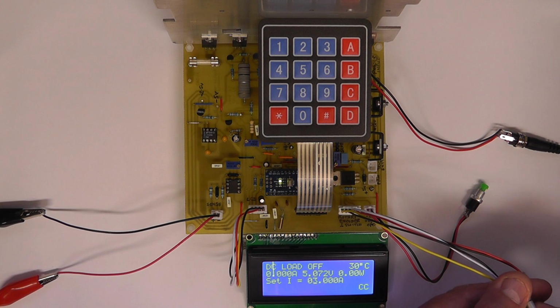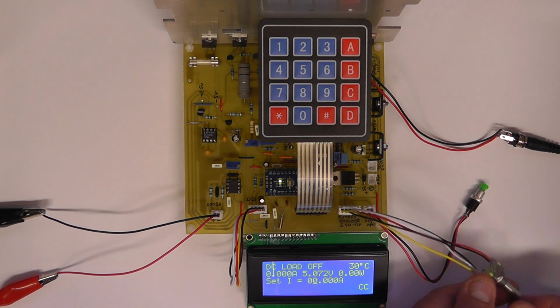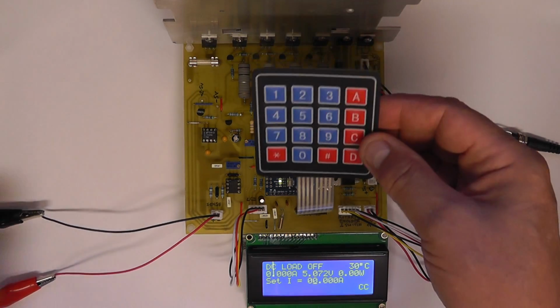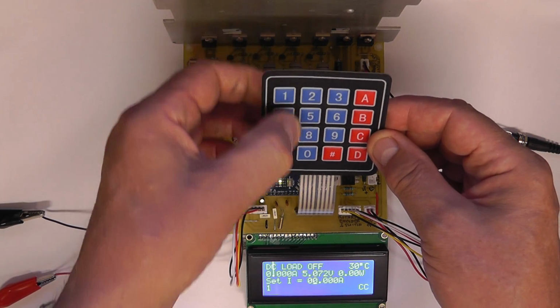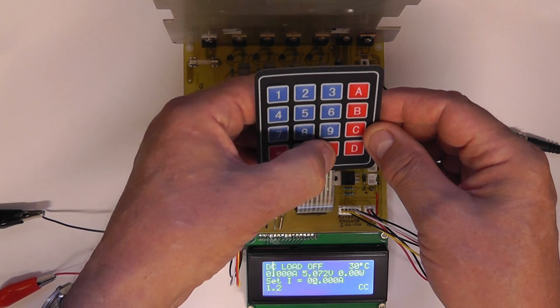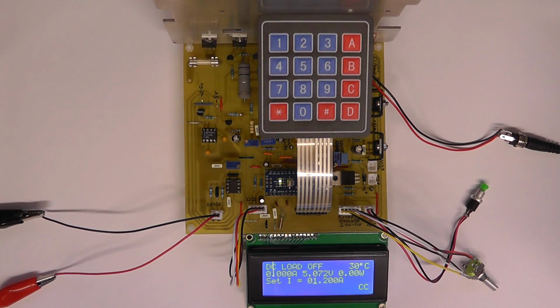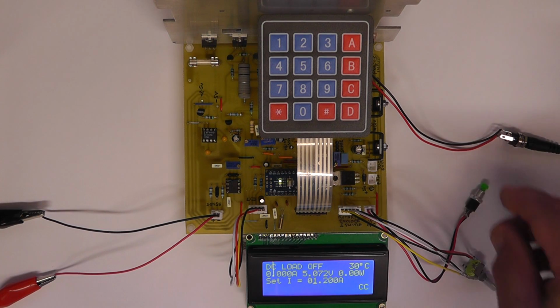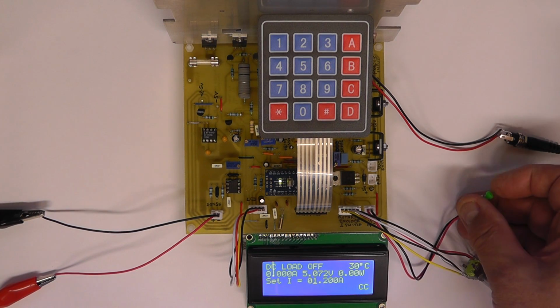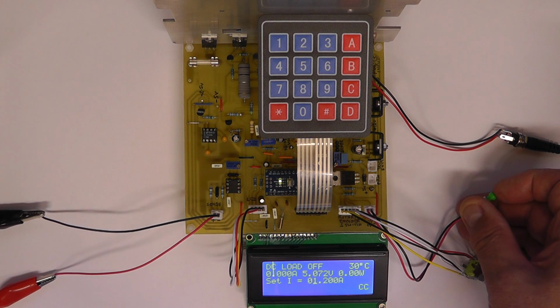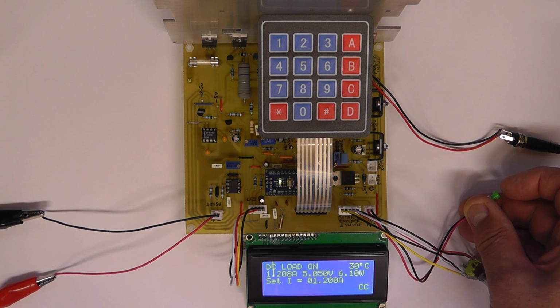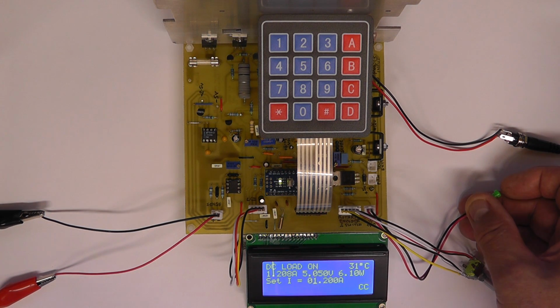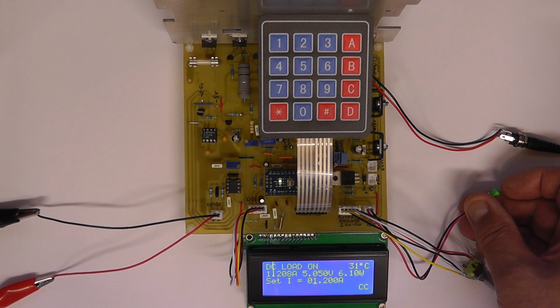I'll set the current back to 0 and just make sure the keypad is working. If I put in 1.2 amps, that seems to be working. Let me switch the load button on and see what reading we get on the current display. At the moment we're getting 1.208 amps, and we set it for 1.2 amps. We haven't done any calibration on this at all yet, so that seems to be fine.